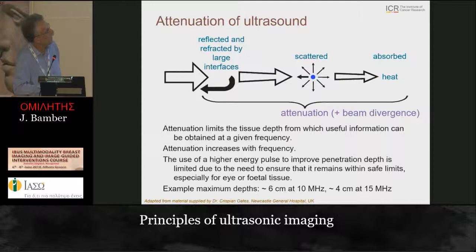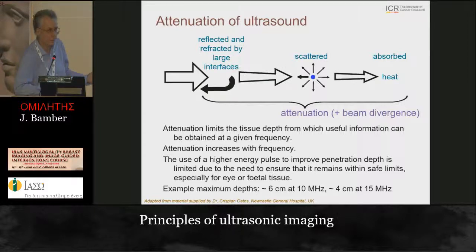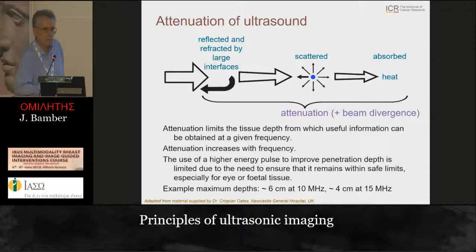Most ultrasound energy ends up being absorbed in tissue, generating a small amount of heat. We are raising the temperature of tissue during ultrasound scanning - that's a safety issue, though not a problem with properly set manufacturer settings. The thermal index and mechanical index are displayed in the top corner of the image. It's worth remembering that the tissue does heat up a little bit.